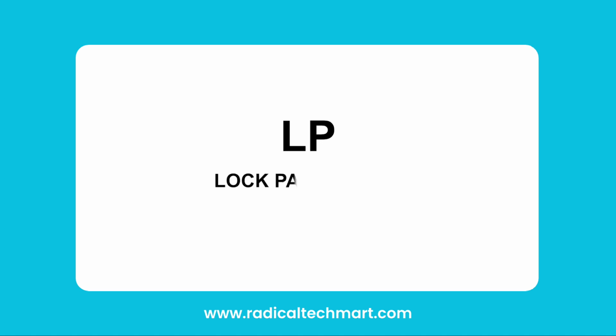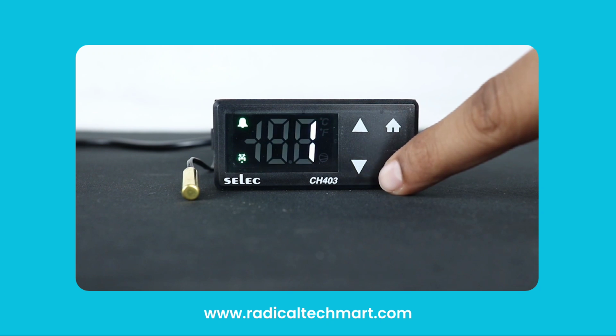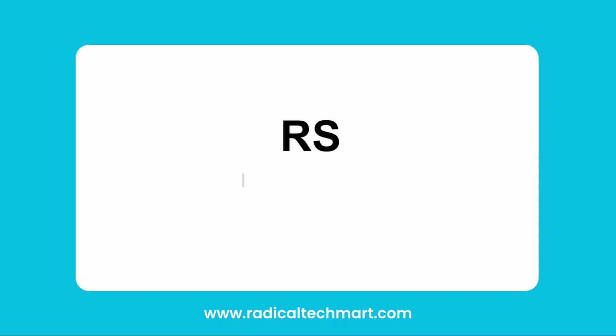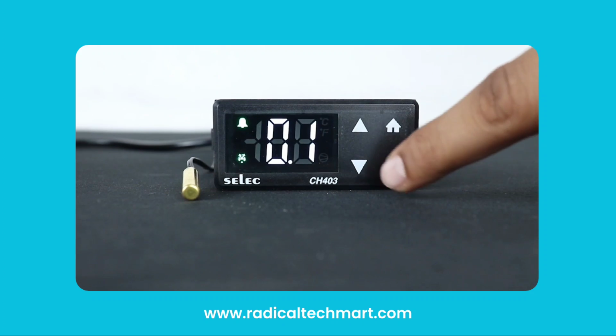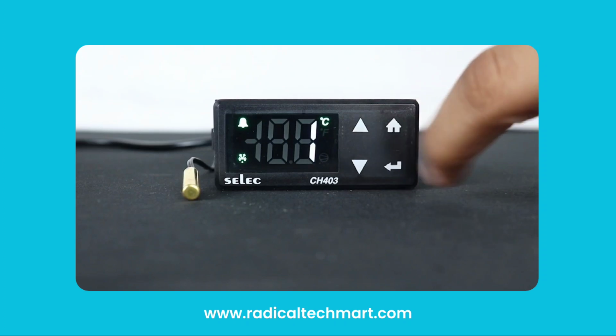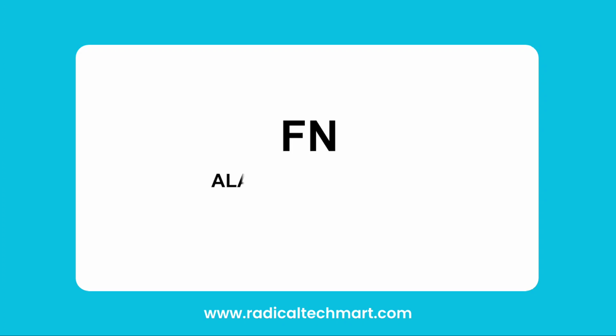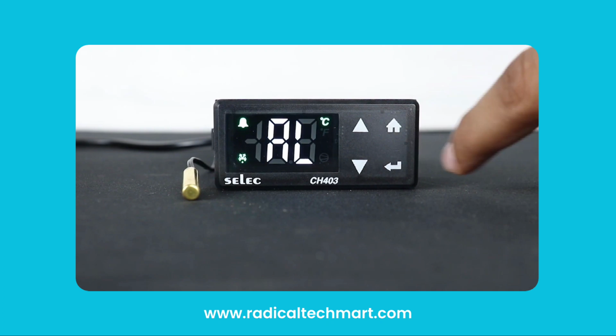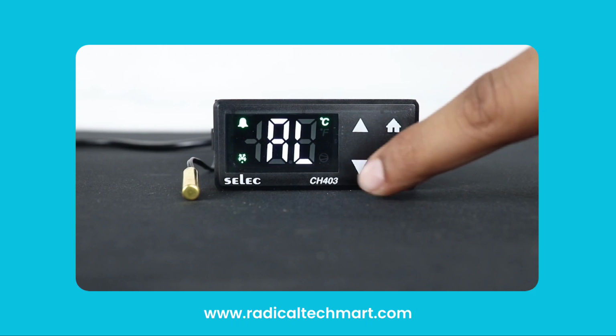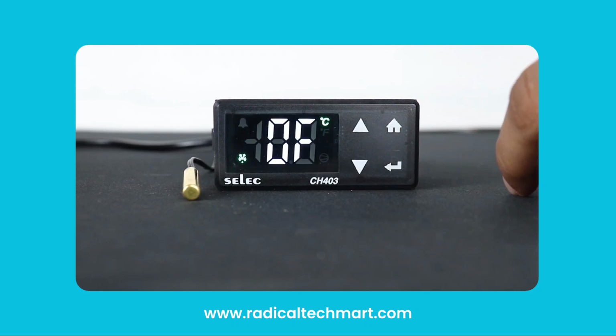Next is LP, which means lock parameter, that enables or disables the editing of the programming parameters. RS denotes display resolution. The user can change either 0.1 or 1 degree as shown in the controller. The next parameter is FN. It is for the alarm indicator. By using this parameter, the user can enable or disable the alarm indication from the display.